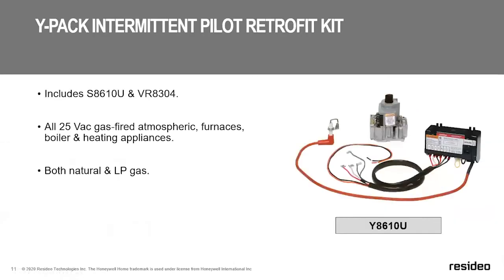Now let's take that gas valve and the 8610U controller, put it all in one box, and add a pilot, a harness, and a cable, everything you would need for a retrofit from a standing pilot system to an intermittent ignition system, which brings a piece of equipment up to code. The nice thing about this is it's all in one little box, everything you need to take any standing pilot system and bring it up to an intermittent ignition system, which is safer and also saves on gas.